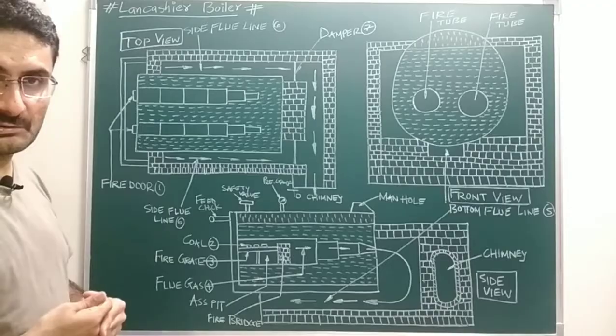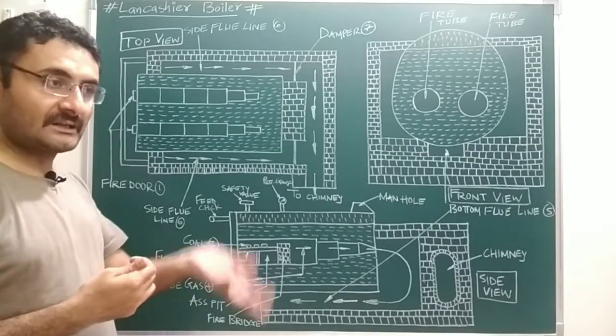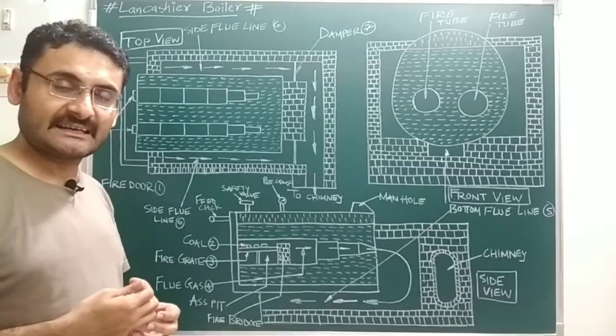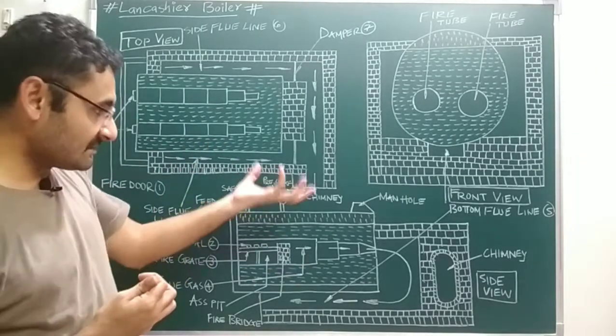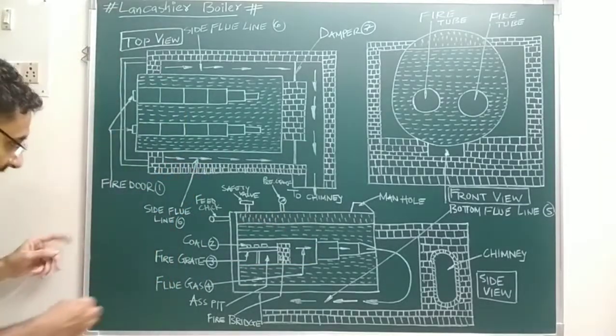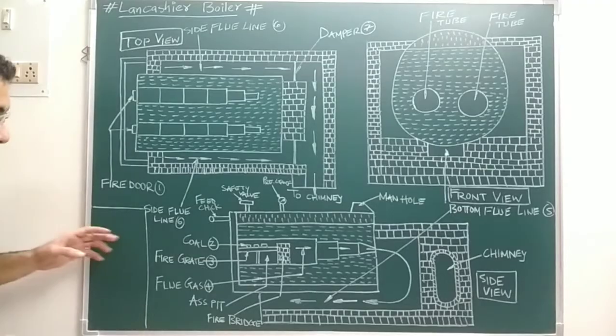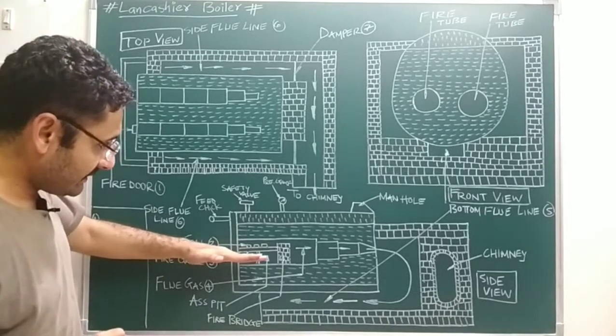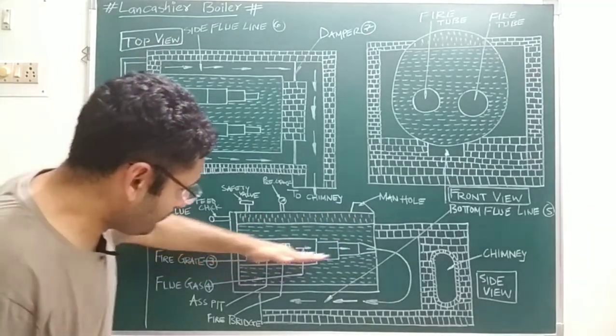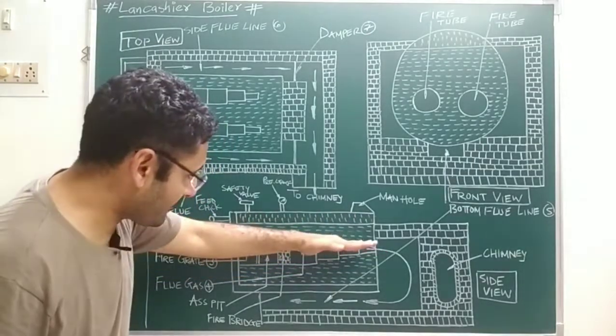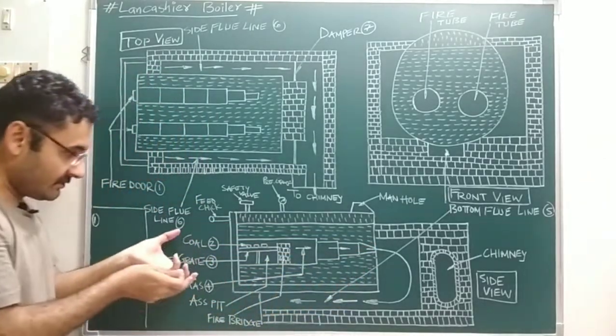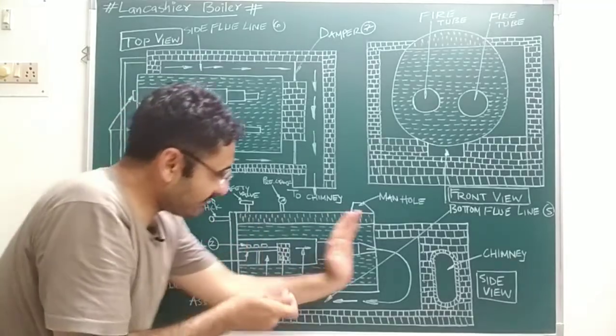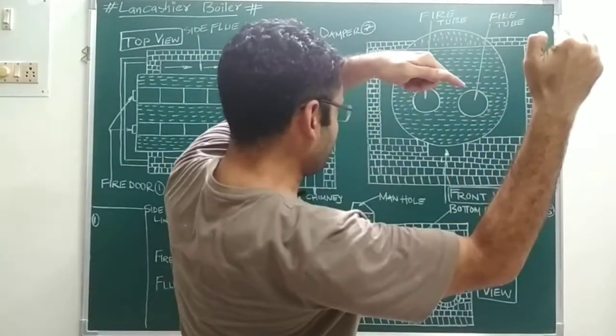Boilers are used to heat water so that it is converted into high-pressure, high-temperature steam. In the Lancashire boiler, heating of water takes place in three stages. In the first stage, flue gases move from front to back inside the fire tubes — combustion of coal takes place at the front, and flue gases travel toward the back.